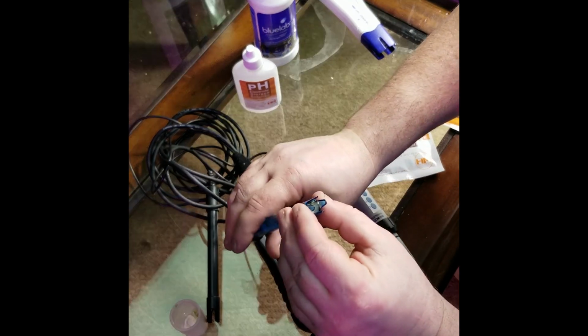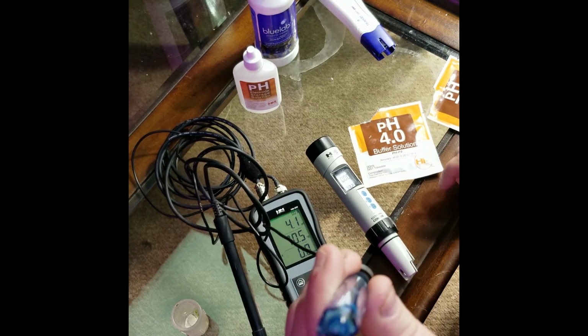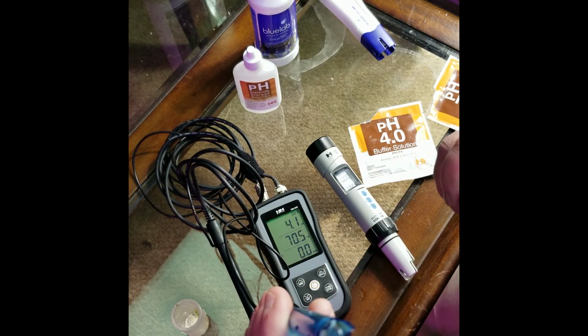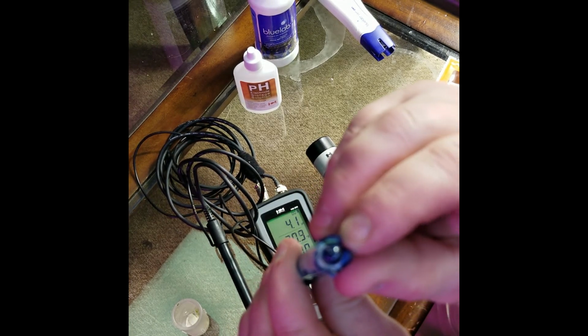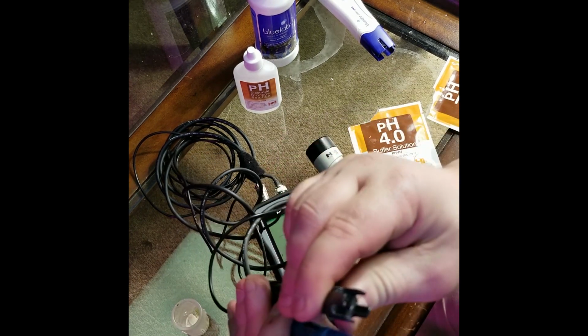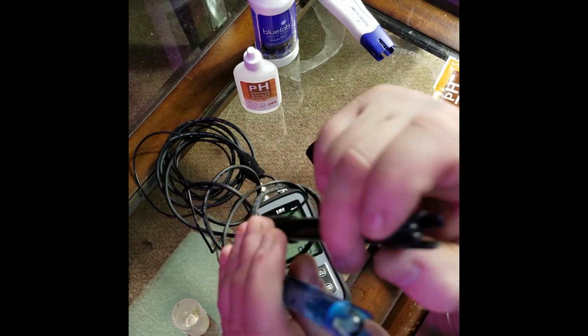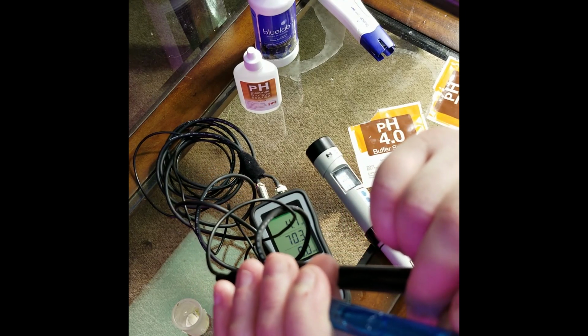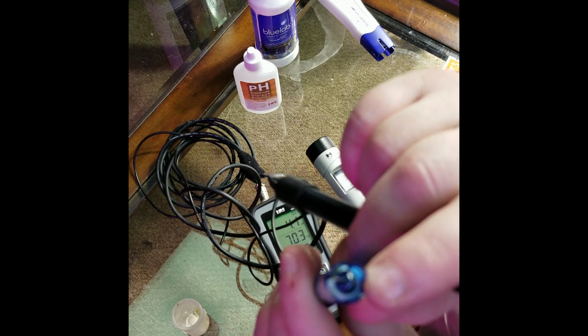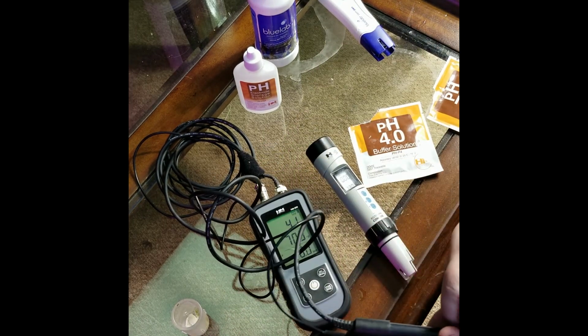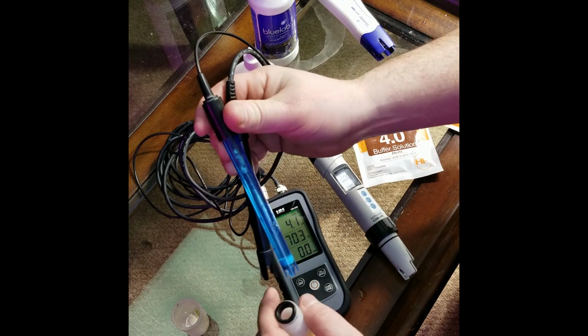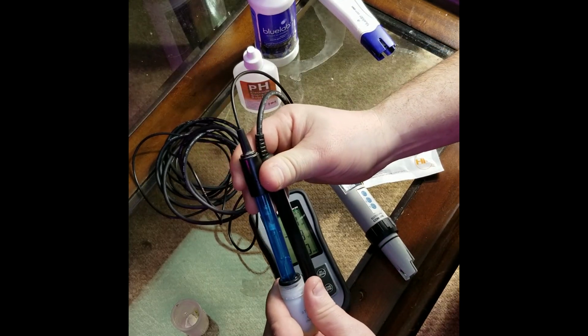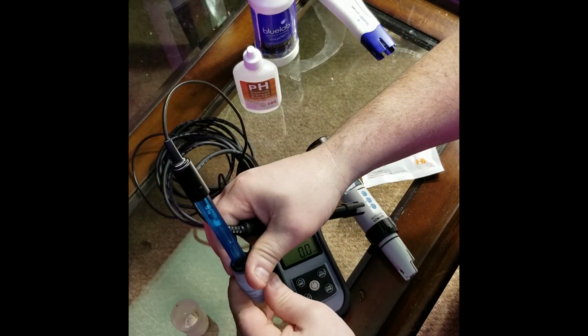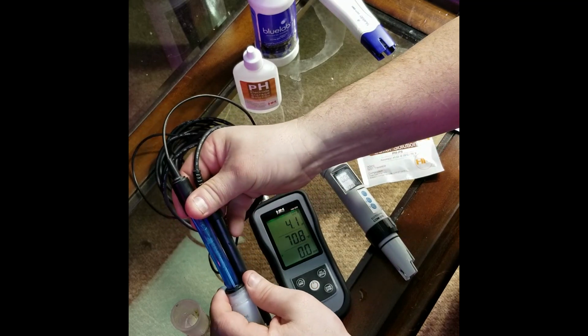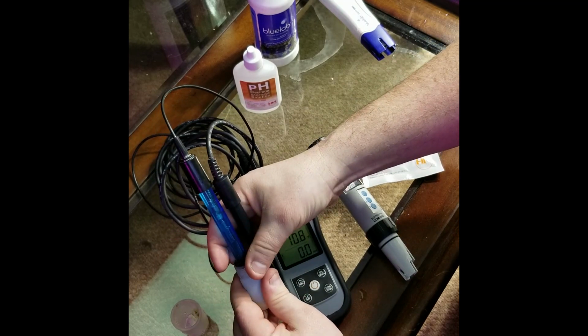So, first thing I recommend people do is very gently take a toothbrush and get into these crevices on both the PPM and temperature probe and in between the glass, but very gently. Just get any debris that might be there out of there. That's first and foremost, and what you'll notice usually is your reading will go right back to being within 0.1 of what it should be calibrated. And that goes for any brand.